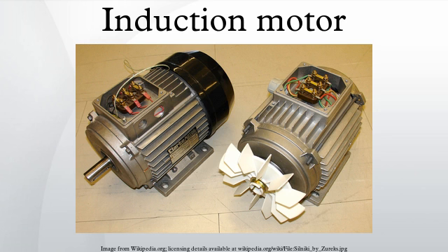Self-starting polyphase induction motors produce torque even at standstill. Available cage induction motor starting methods include direct online starting, reduced voltage reactor or auto transformer starting, star-delta starting or, increasingly, new solid-state soft starter assemblies and, of course, VFDs.